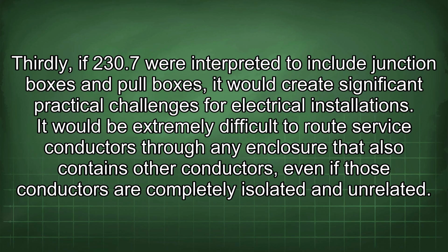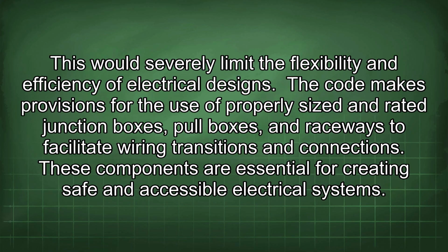Thirdly, if 230.7 were interpreted to include junction boxes and pull boxes, it would create significant practical challenges for electrical installations. It would be extremely difficult to route service conductors through any enclosure that also contains other conductors, even if those conductors are completely isolated and unrelated. This would severely limit the flexibility and efficiency of electrical designs.